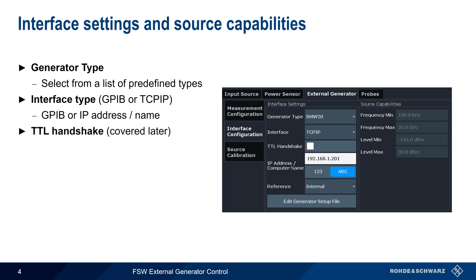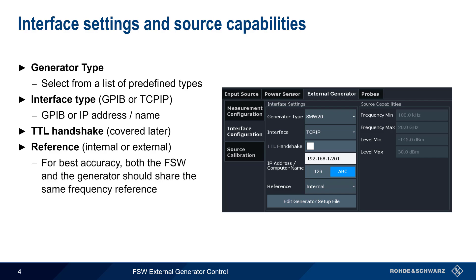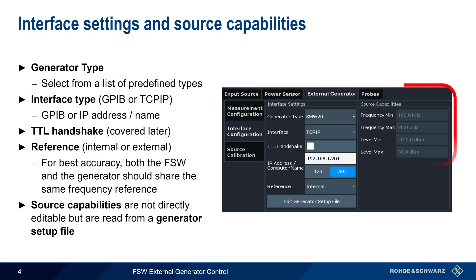TTL handshake is a topic we'll come back to in a few minutes. The type of frequency reference can also be configured. Internal uses the FSW's own internal frequency reference, but for best accuracy, the FSW and the generator should share the same frequency reference. Note that source capabilities of the selected generator are shown but are grayed out, because these parameters are not directly editable, but rather are read from a generator setup file.